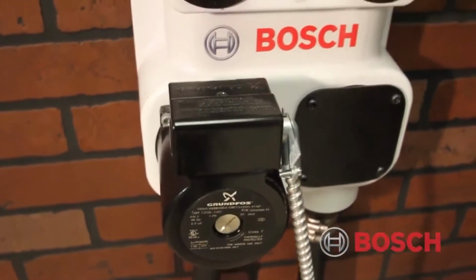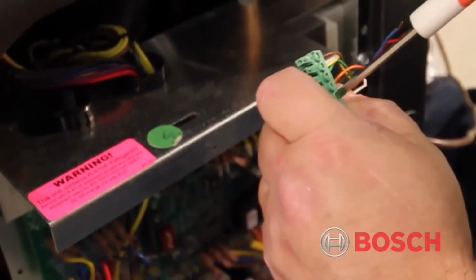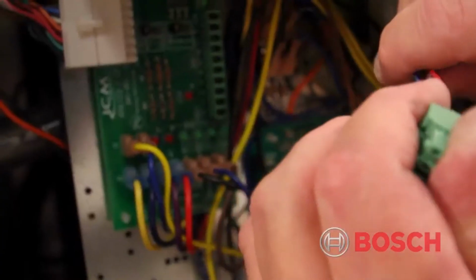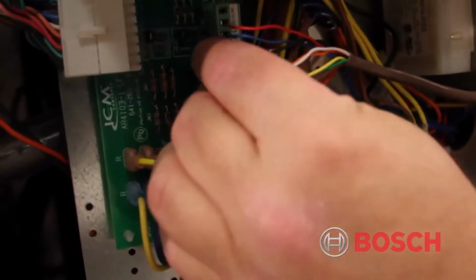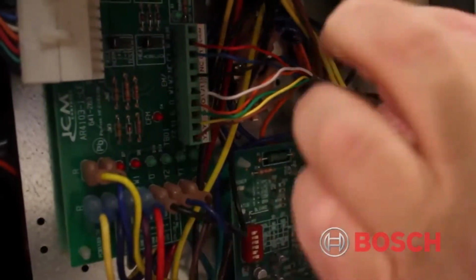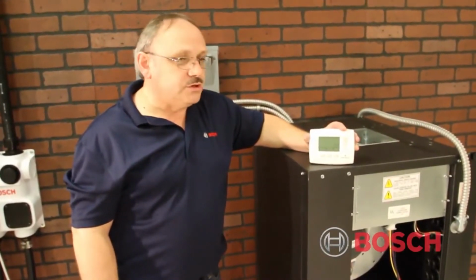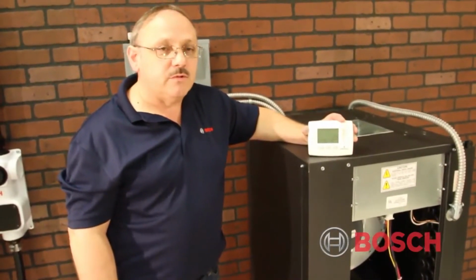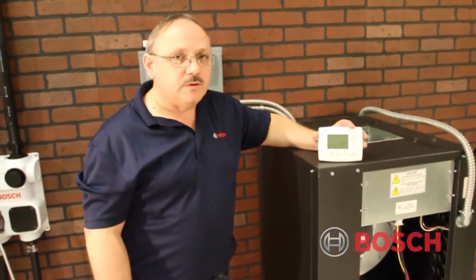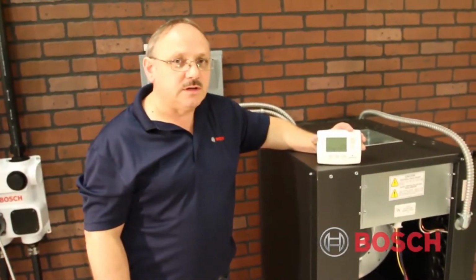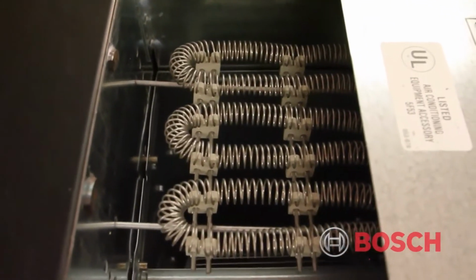in the electrical box. At this point, we're going to install our thermostat. We have already made our thermostat connections at the equipment on the low voltage terminal block located on the ECM motor control. We have several thermostats available from Bosch, anywhere from a simple digital control to the programmable thermostats that are actually touchscreen. And any control that you use, you want to make sure you select the control that matches the number of stages that you have to operate with your equipment. In the case of the TA25, which we're installing today, it is a 2-stage heat and 2-stage cool unit. It also has an additional 3rd stage of heat that is factory installed, that is the heat strips. So we will actually have to have a thermostat that is capable of 3 stages of heat and 2 stages of cool.